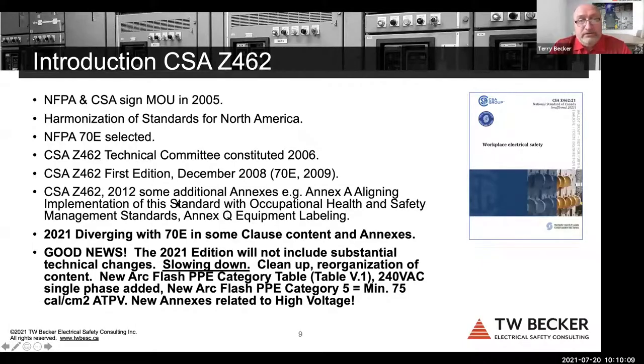We did take some divergence in the annexes right away, basically. So we have annexes in Z462 that are not in 70E, and we added some new annexes that are not in 70E related to high voltage electrical equipment, right? And that's good news because we want to make sure that users understand that 70E and Z462 apply to both low voltage and high voltage enclosed electrical equipment. And there is some information that can be applied to high voltage outdoor substations as well, but it really doesn't apply to transmission and distribution.